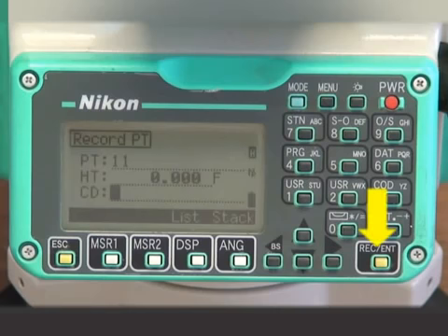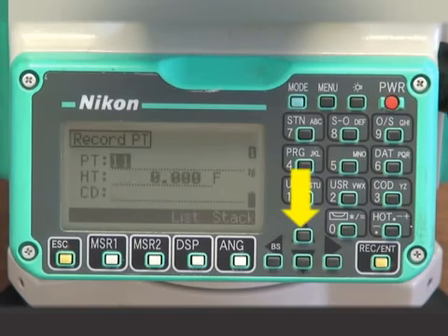When you press the Record Enter button, the instrument brings up the Data Entry menu. Here you can renumber the data point and/or name it as well. It is important to remember that the Nikon NPL 352 will increment that last known data point for each measurement. As our last point entered was number 10 for the instrument location, the instrument wants to assign 11 as the next measured point number. Simply highlight the number by pressing the up or down keys and change this number.